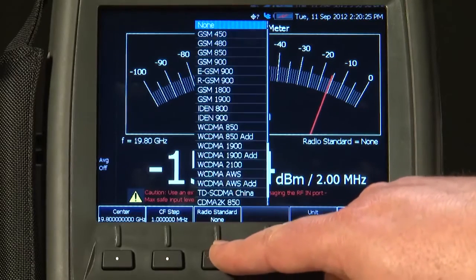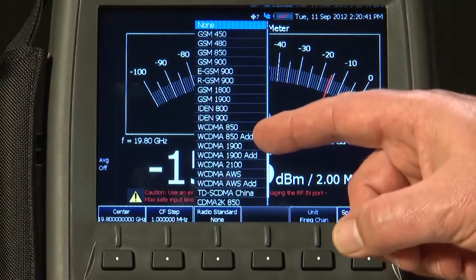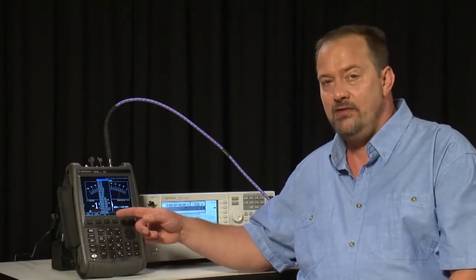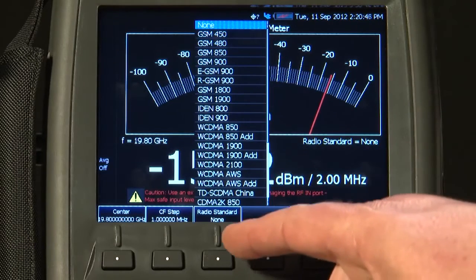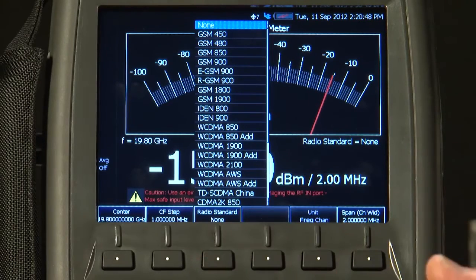And one final thing I will point out that is available in both the channel power meter and in the spectrum analyzer options is the radio standard here. If you are working in one of the commercial radio standards such as GSM, WCDMA, or whatever, then if you do not know the frequency of the channel you are in, you can just select that radio standard and then enter the frequency by channel number instead of in MHz.